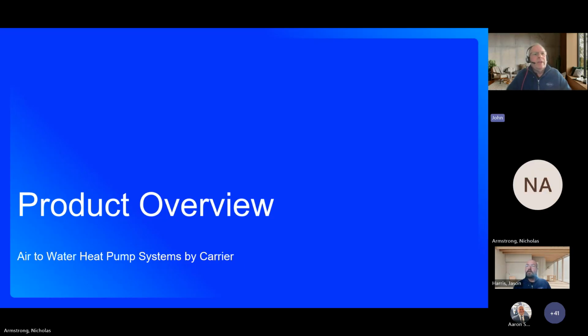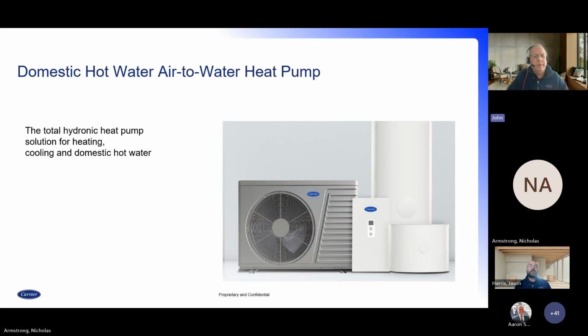So we're going to take a look at some of the breakout of what makes up the kit for this product, and so we'll move forward. First will be the outdoor unit, but just before we get to that, we have the bits and pieces of the kit. We have an outdoor unit. It's the larger two components to the left. A smaller of the two there is an indoor unit, which communicates to the outdoor unit. It does this through what's called a Modbus communication, and all the information from the outdoor unit is communicated into the indoor unit for that cockpit type of interaction.